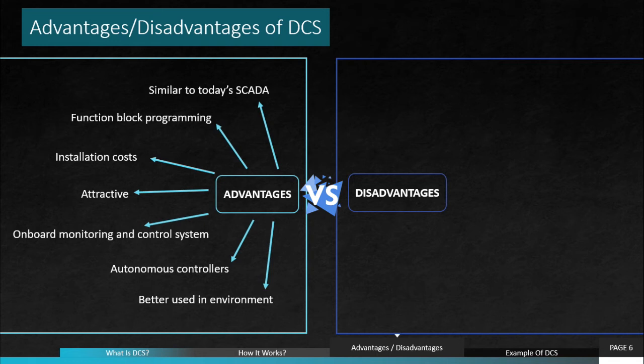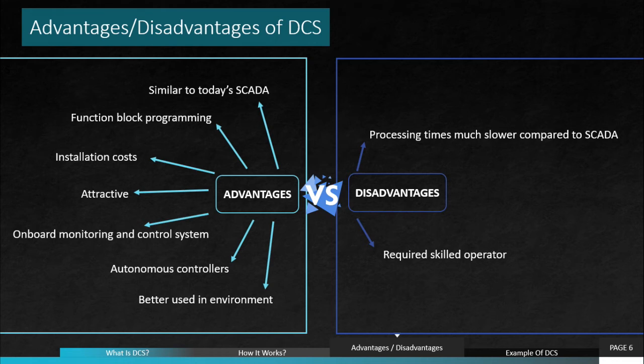Then the first disadvantage of the distributed control system is that processing times in DCS are much slower compared to SCADA. Next, DCS requires skilled operators since all the information is hidden behind the CRT. The CRT acts as the operator interface that gives many advantages to the control and operation of a plant process. However, the CRT may lead to operator errors and also reduce operator performance. Then it will cause plant upsets and loss of life.